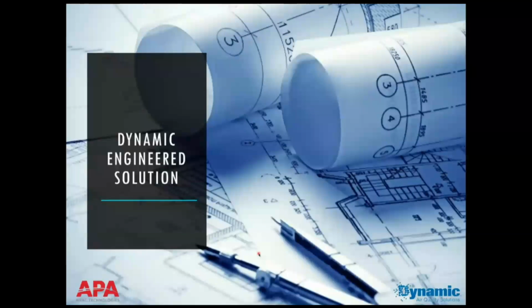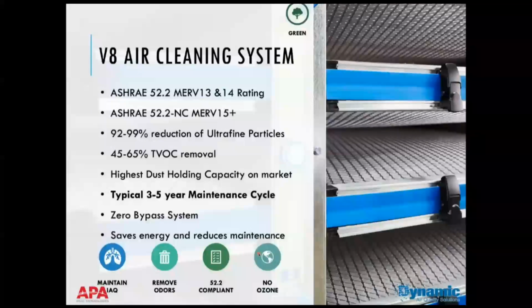So what is it that we have that can be some tools that might be able to help out in all this? We have a range of systems. We have things geared towards particle filtration, gas phase, UV systems. We have a range of systems that we use for various applications. So in this particular instance, probably our lead product would be the V8, which is a modular polarized media air cleaning system that would install in the filtration section of an air handler. In a standard MERV test, we have MERV 13, 14 versions. In actual operation, due to the various mechanisms, it's more like 15.